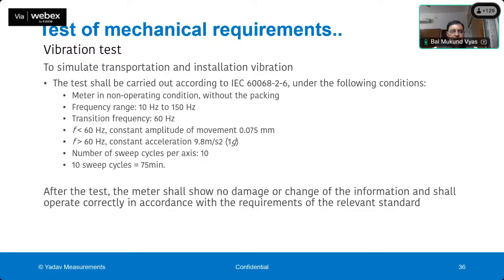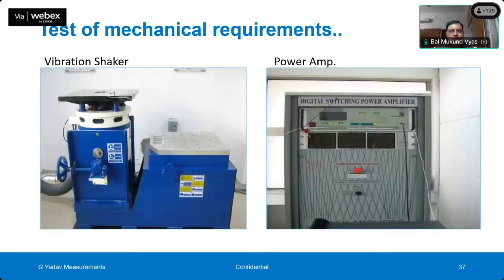And there are 10 sweep cycles from 10 Hertz to 150 Hertz, then 150 Hertz to 10 Hertz, and so on. The meter is subjected to 10 such cycles. So this total test actually lasts for 75 minutes. The meter is subjected to vibrations on a vibration machine for 75 minutes, and after that the meter is tested for its accuracy and any damage in the meter. If there is damage and change in accuracy, then it is not a suitable meter. So these pictures are showing you vibration, and the vibration is done in all three axes of the meter, X, Y, and Z, as the meter can face vibration at different angles also.